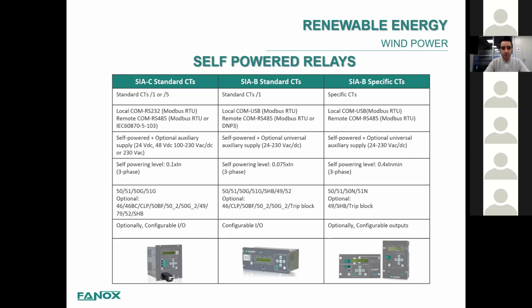This is the portfolio of self-power relays from Fanox. As you can see, we have a SIA-C that works with the standard CTs, /1 or 5 amps. All of our self-power relays have remote communications, Modbus or IEC 103 or DNP3, and all of them are self-powered, but also have the option to have an auxiliary power supply. They have different self-powering levels depending on the CTs and the relays you are choosing for your application.